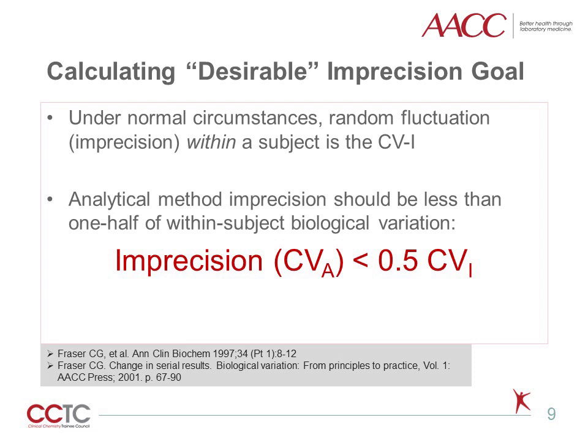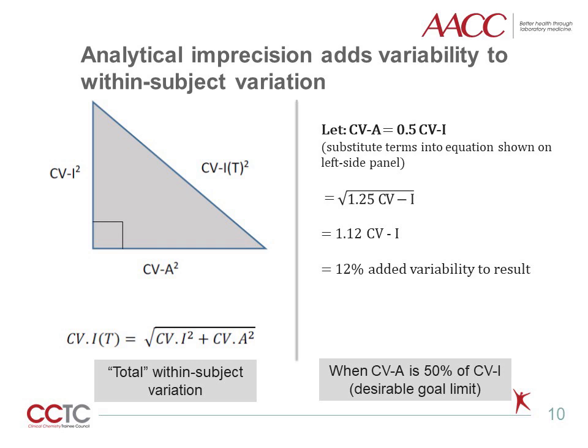The first calculation is setting the desirable imprecision goal, which is based on the CVI estimate for the test biomarker. CVI represents a distribution of repeated test values taken from the same subject, ideally reflecting pure human biology only. In practice, analytical variation CVA of the test method contributes variation to the CVI estimate. Because of this relationship, it has been recommended that the desirable analytical imprecision goal should be less than one-half of within-subject biological variation.